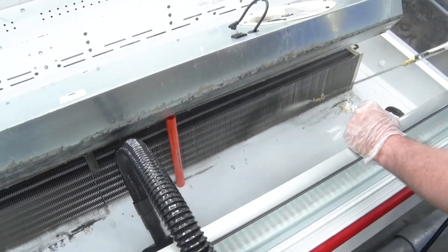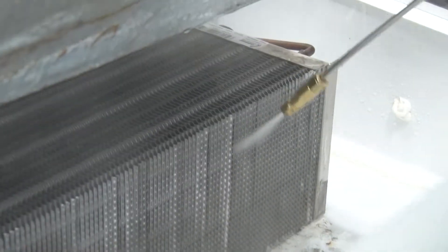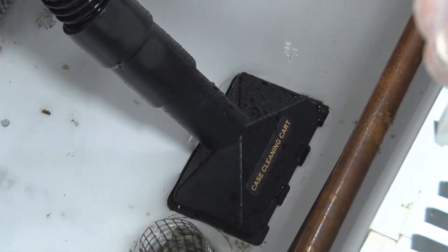For proper cleaning, the indoor pressure washer is used to flush dirt and organic contaminants from the fan housing and condenser coils. The liquid soil and other matter is removed by the wet vacuum, preventing soils from entering the case drain which could lead to potential clogging.